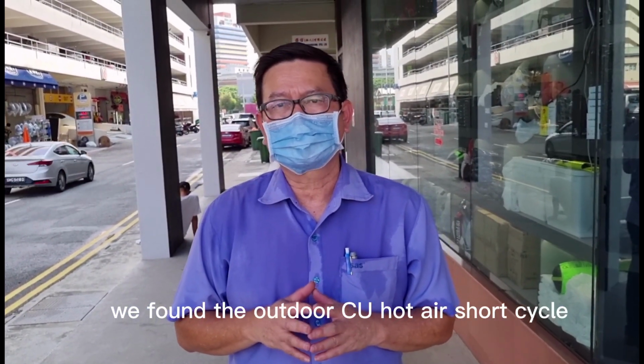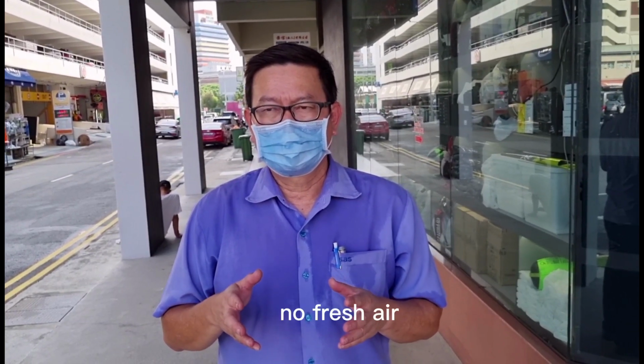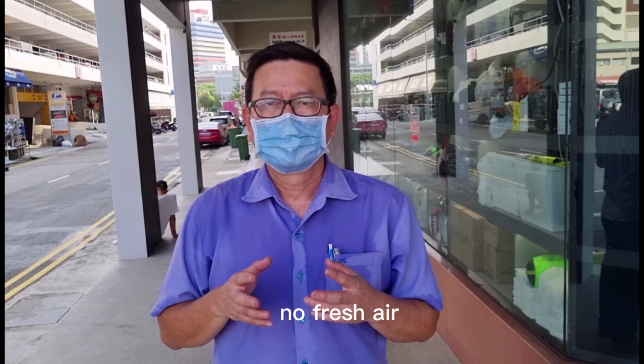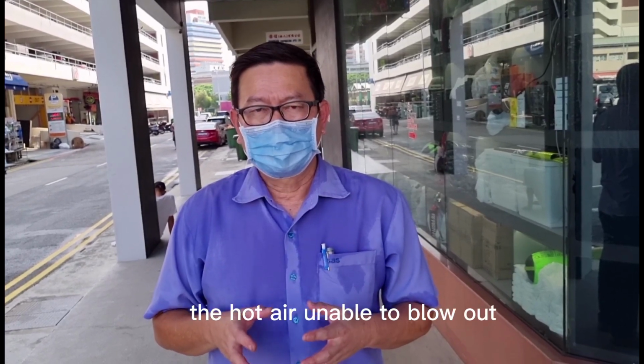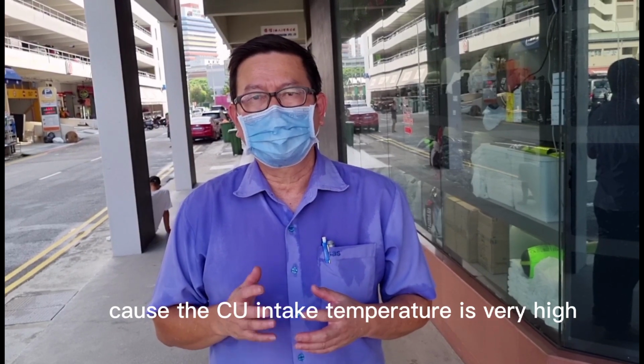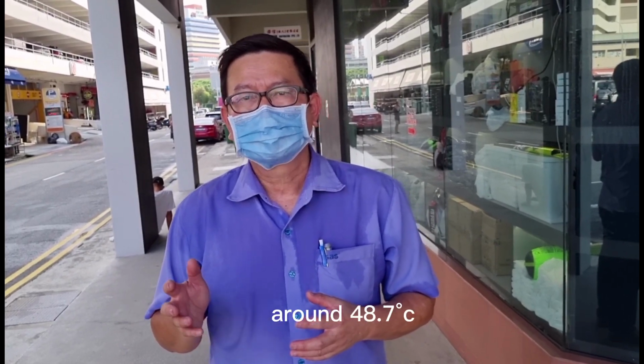We found the outdoor condensing unit has hot air short cycle, no fresh air, and the hot air unable to blow out, causing the intake temperature to be very high, around 48.7 degrees.